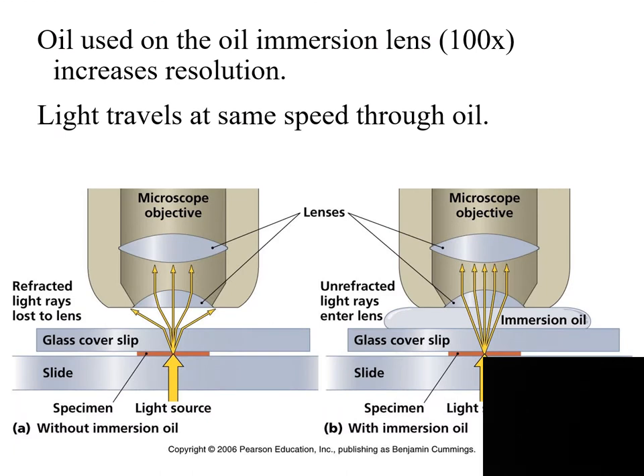The oil immersion lens uses oil to increase resolution. Light travels at the same speed through the oil, which helps to increase the sharpness and contrast of the image. If you look at the image without oil, only three rays are captured by the objective lens, whereas with oil, five rays are captured. Therefore, the oil helps to increase resolution, contrast, and sharpness.